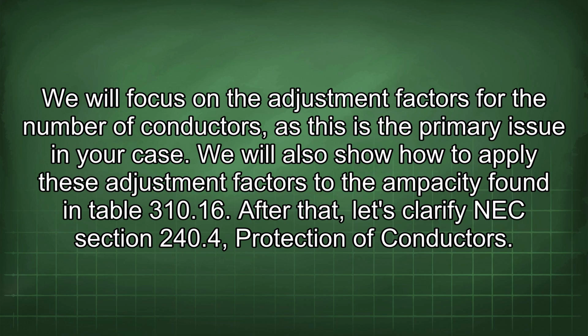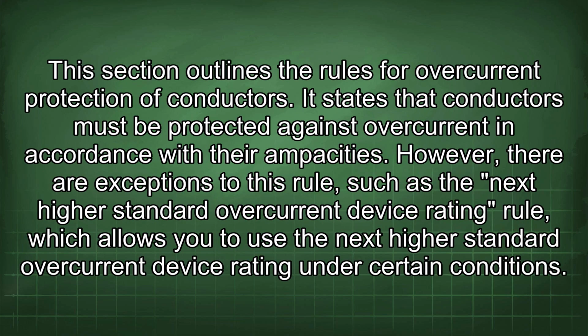After that, let's clarify NEC Section 240.4, Protection of Conductors. This section outlines the rules for overcurrent protection of conductors. It states that conductors must be protected against overcurrent in accordance with their ampacities. However, there are exceptions to this rule, such as the next higher standard overcurrent device rating rule, which allows you to use the next highest standard overcurrent device rating under certain conditions.